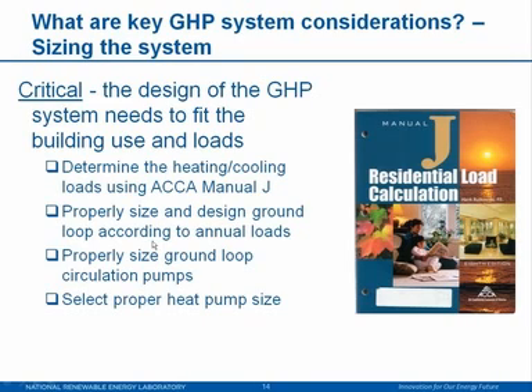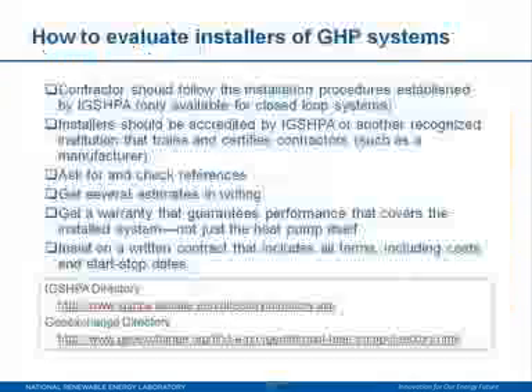Then you also want to make sure that the ground loop is circulating the heat transfer fluid properly. You want to make sure that the circulation pumps hooked up to the ground loop are properly sized. If they're oversized, they use far more electricity than should be required. If they're undersized, they will not meet the heating and cooling loads of the structure. And then you also want to properly select the heat pump size for the structure and loop field that you're putting in.